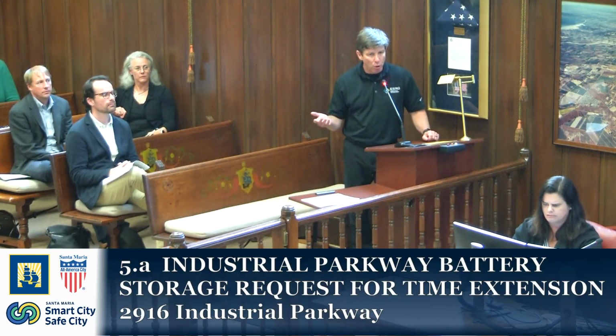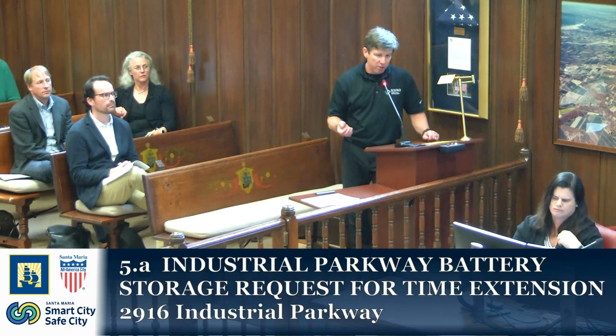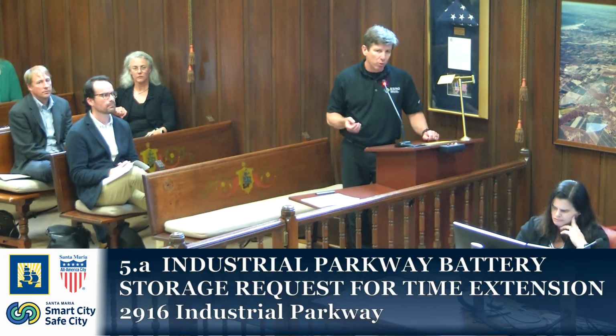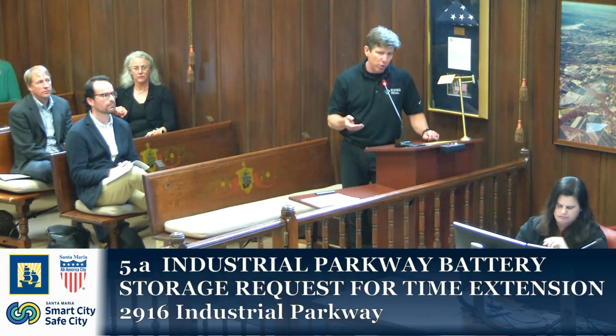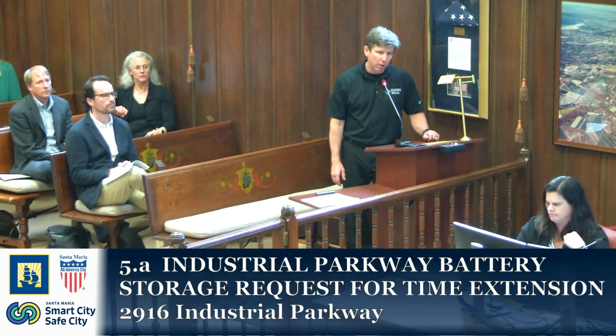If the smoke and heat detector is activated, that would alert the fire department for a response. That would also activate an aerosol fire extinguishment system inside the unit. Now, that doesn't actually put out battery cells, but if there were ever an incidental fire, like in the electrical system, it would extinguish that before anything involved the cells.